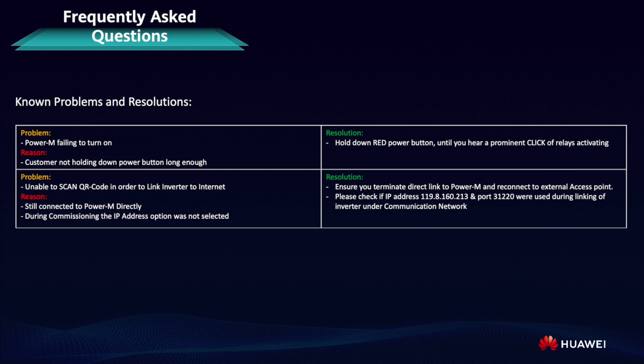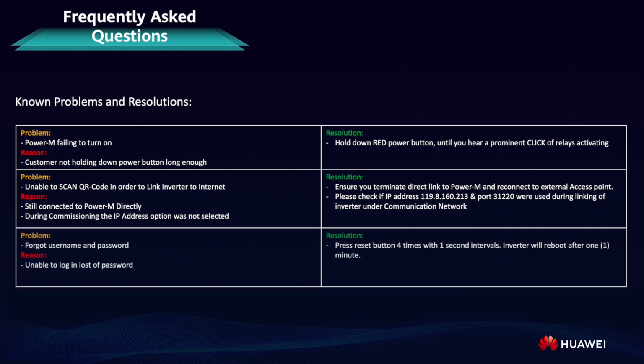Please check if the IP address 119.8.160.213 and port 31220 were used during linking of the inverter under communication network. Forgot username and password. Reason: unable to log into the system. Resolution: press reset button 4 times within 1 second intervals. The inverter will reboot after 1 minute.